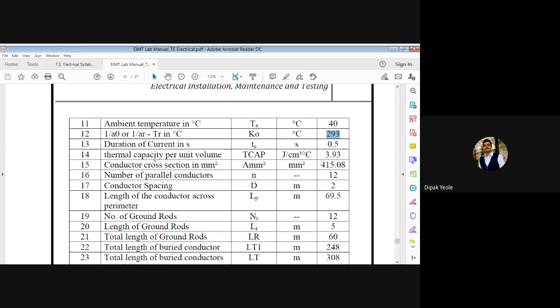Thermal capacity we need, the conductor cross section area we need, the number of parallel conductors we need, the conductor spacing we need. Also, we need the length of conductor, number of ground rods, length of ground rods, total length of ground rods, total length of buried conductors, total length of buried conductors and rods, maximum length on the x-axis, maximum length on the y-axis, area of the grid. So you can see over here, the area is 247.5 meter square. Yes. And then we need one decrement factor, which is 0.415. It has no unit, so it is a unitless quantity.